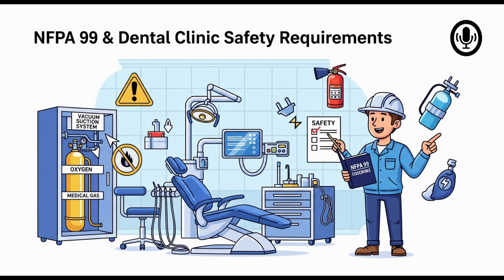Wow, that sounds painstaking. It is, but absolutely necessary. Imagine getting pure nitrous oxide when you expected air. Then there are initial piping purge tests. You flow a high volume of gas through each outlet to blow out any dust or debris left from construction, catching it on a white cloth to visually verify cleanliness. Purity tests. For medical air, you test to ensure it meets the standards for dryness, dew point, carbon monoxide levels, and other contaminants. Alarm tests. You simulate fault conditions, low pressure, high pressure, pump failure, etc., and verify that all the required visual and audible alarms activate correctly at the source and on the master panel.